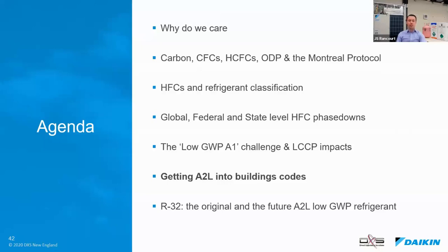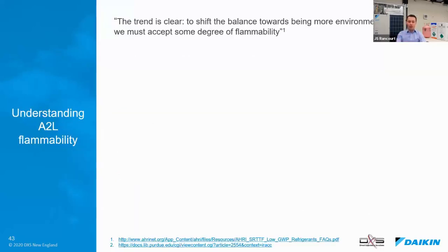So this takes us to, we've got to get A2L into the building codes if we're going to get lower GWP refrigerants into our buildings. So first, we have to understand flammability and the A2L. Here's an interesting quote from an AHRI article. There's a link at the bottom there. I strongly recommend you read that article because it gives you all sorts of good guidance. To shift the balance towards becoming more environmentally friendly, we must accept some degree of flammability. And to some, that might seem a little scary, rightfully so.